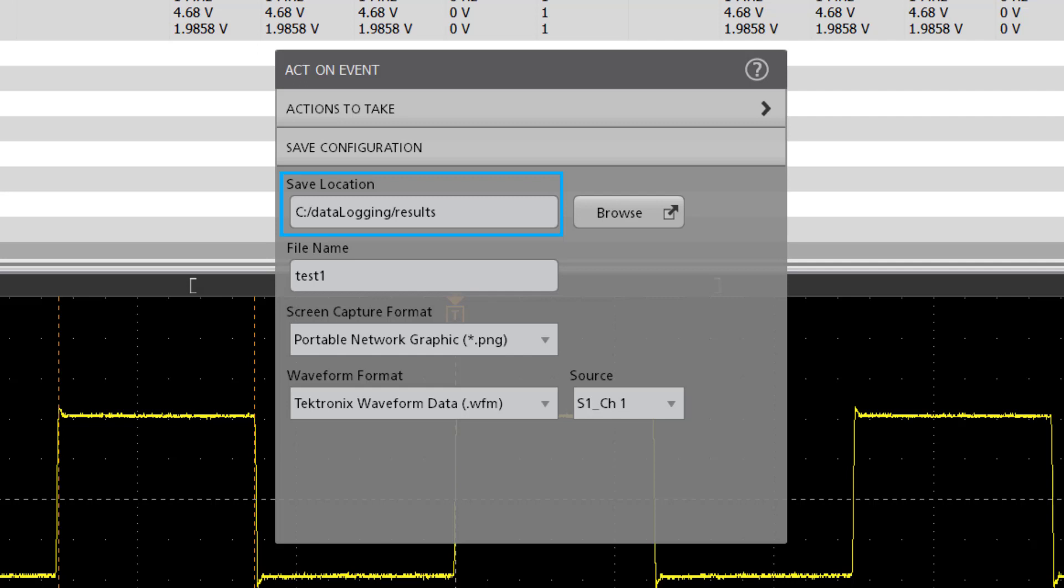Define the location where you want your results to be stored. You can define file naming conventions and even the file format for your screen and waveform captures. You also have the option to capture all the channels or a specific channel. Since we're dealing with only one channel in this demo, I will go ahead and select channel 1.